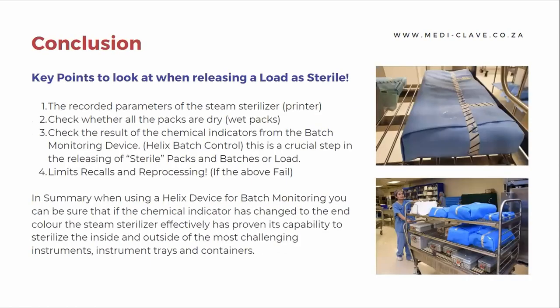So in conclusion, key points to look at when releasing a load as sterile. Firstly, you'll look at your autoclave printout. Does it say that it's passed? Is it saying a failure? Then the next thing to look at is wet packs. Are all your packs dry? And if they are not dry, they need to be reprocessed. So over here in this picture, you can see a nice wet puddle. A wet pack is considered an unsterile pack. So this is unsterile, which will be reprocessed.